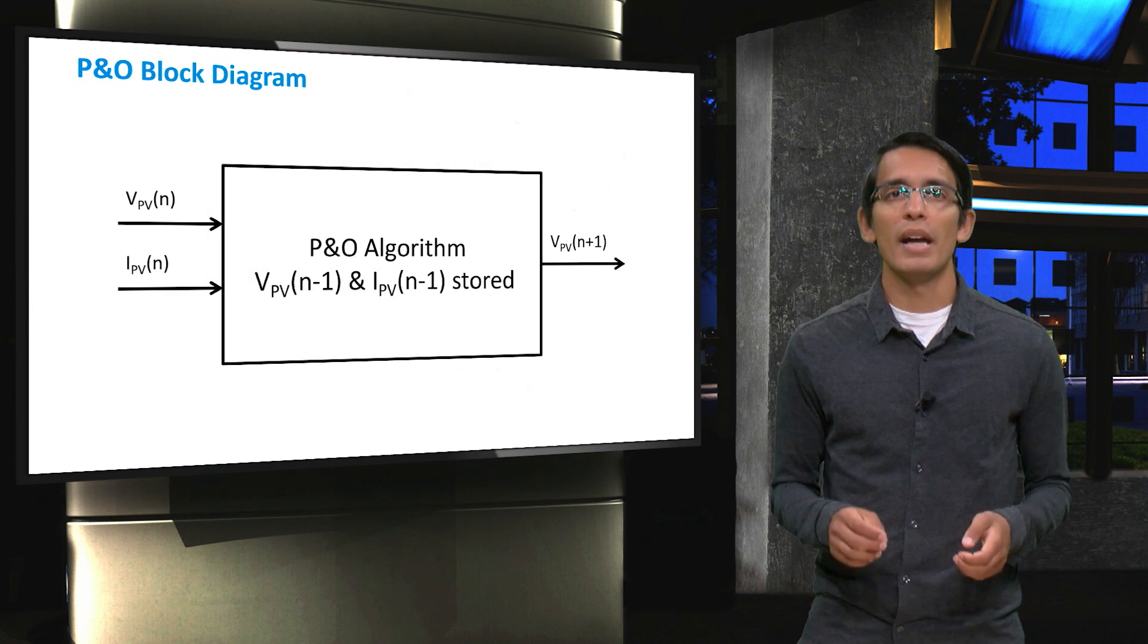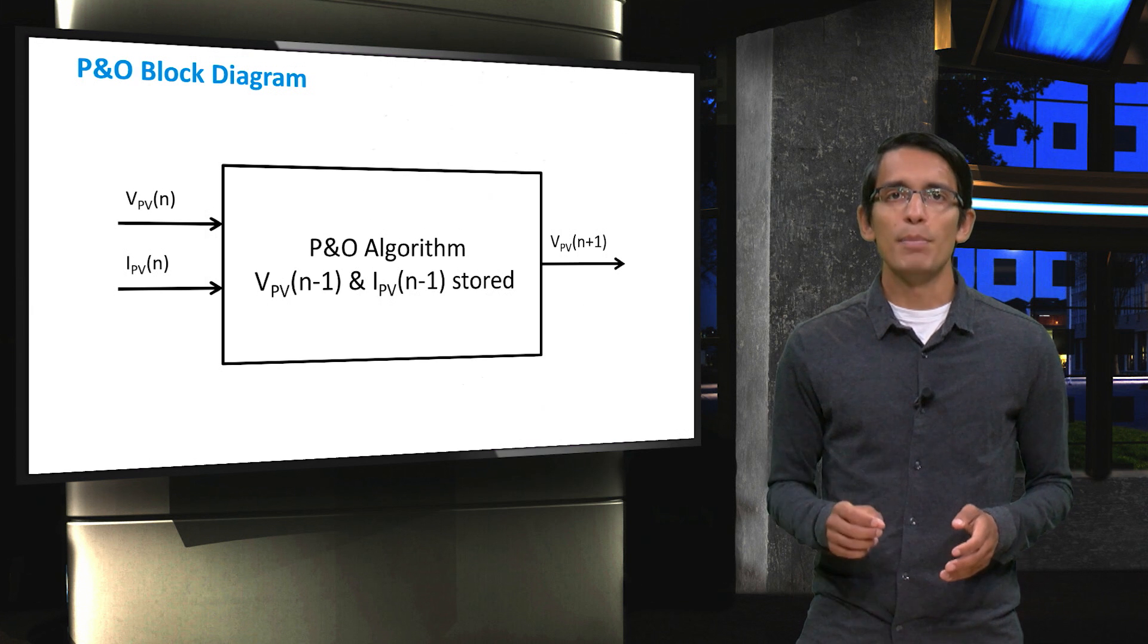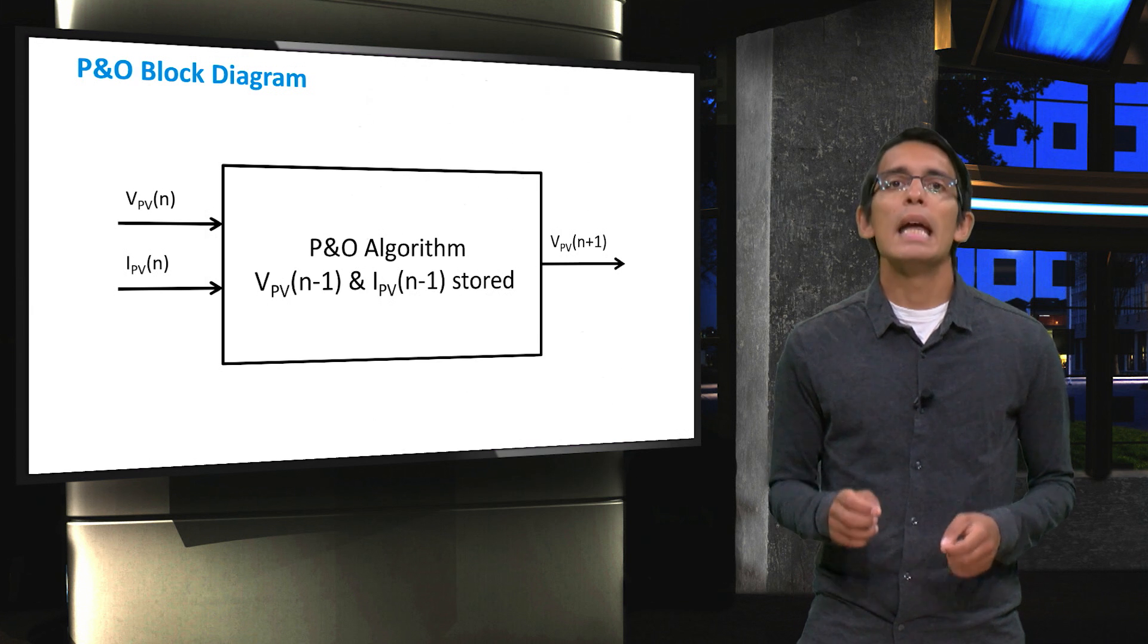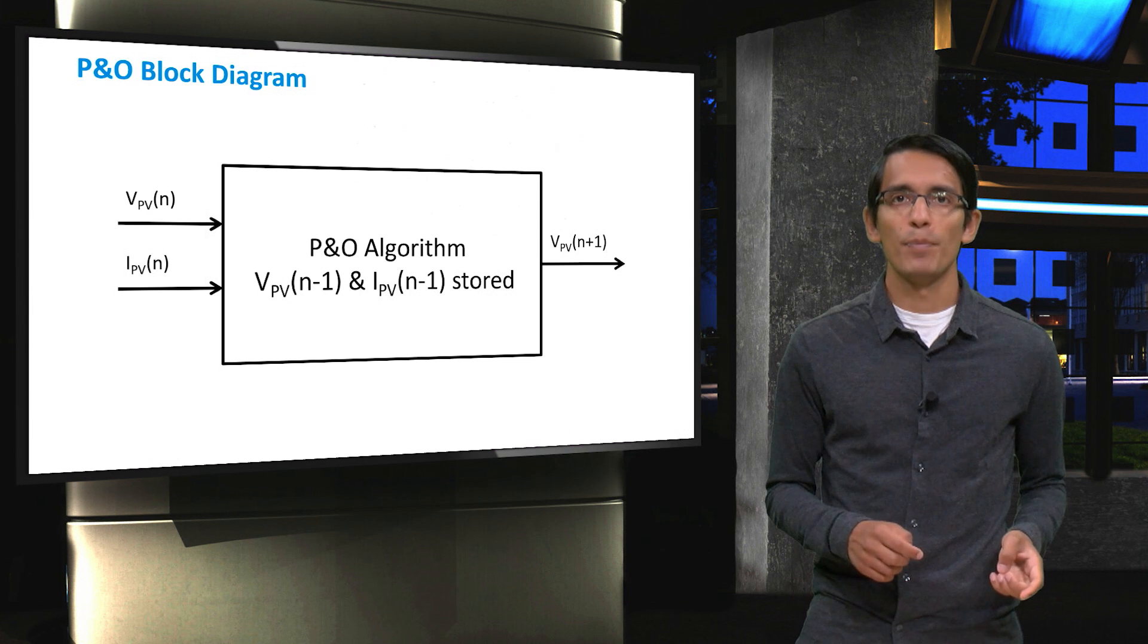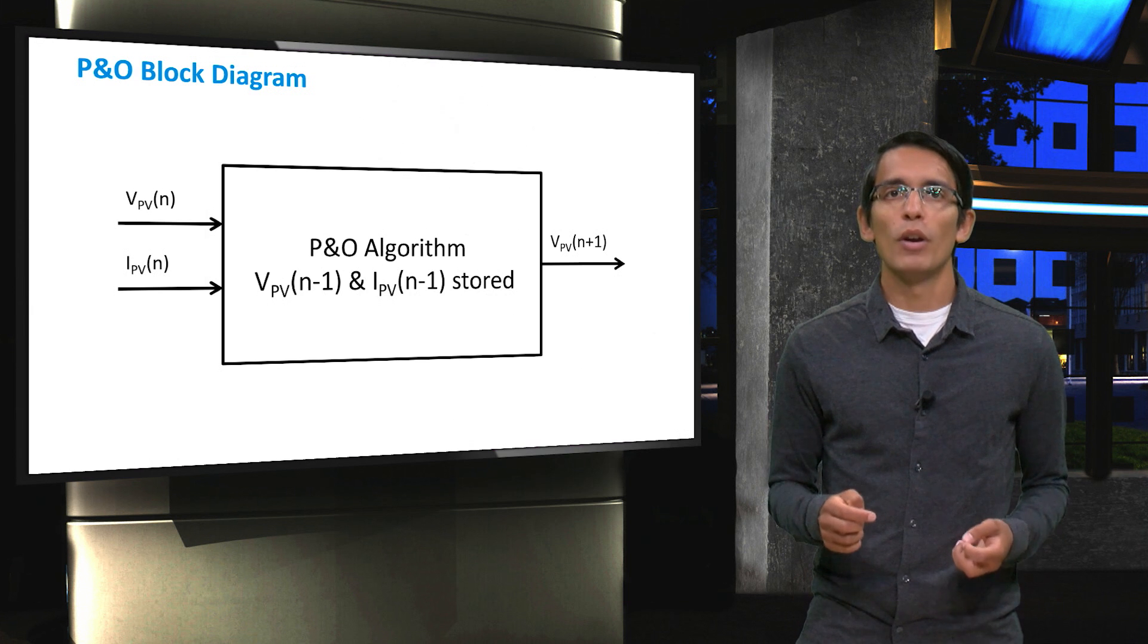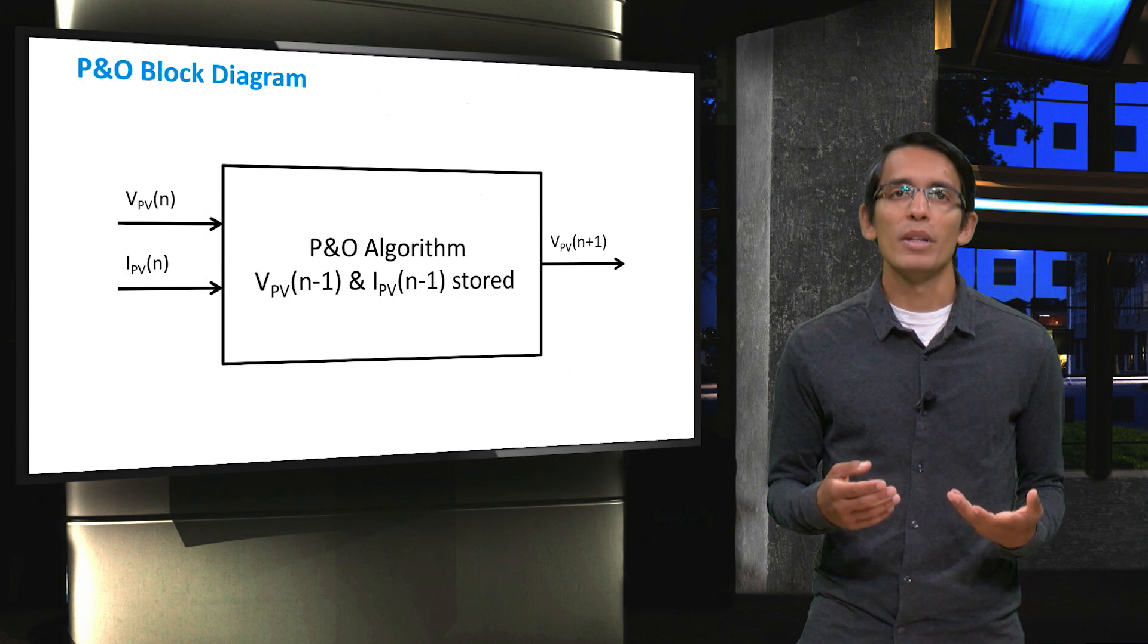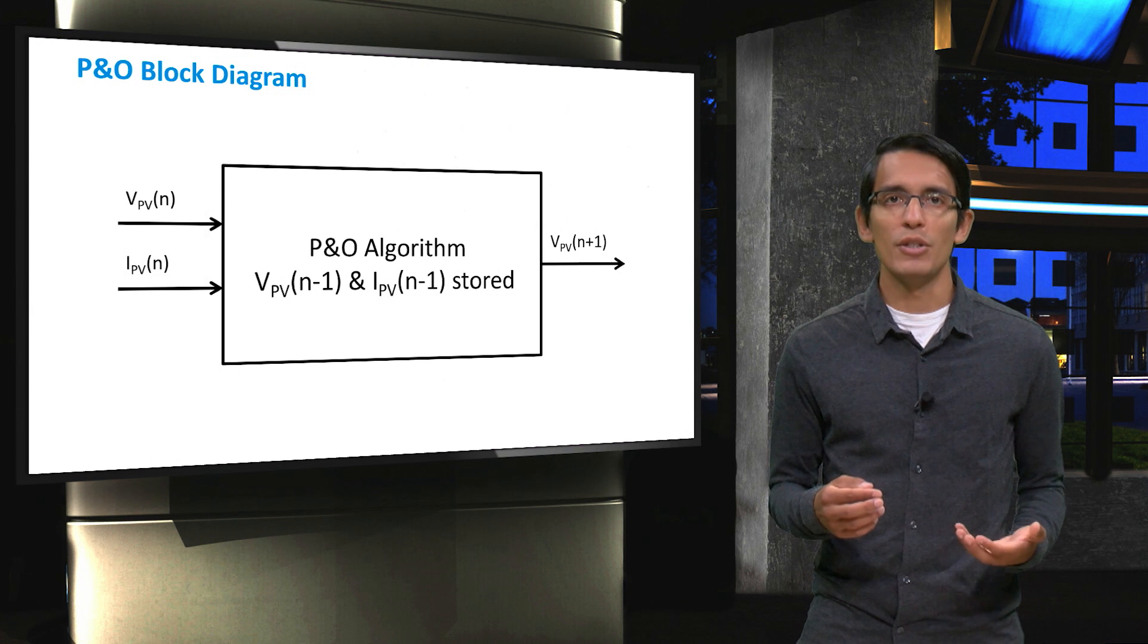Here you can see the block diagram used for the perturb and observe technique. As inputs, it needs the instantaneous voltage and current of the solar cell. It also needs to store the voltage and current before the previous perturbation. Using that, it can calculate whether the current perturbation was positive or negative, and therefore it can decide which direction the next perturbation should be. The logic can also consist of other, more advanced aspects, such as the size of the perturbations depending on some other data stored in memory.